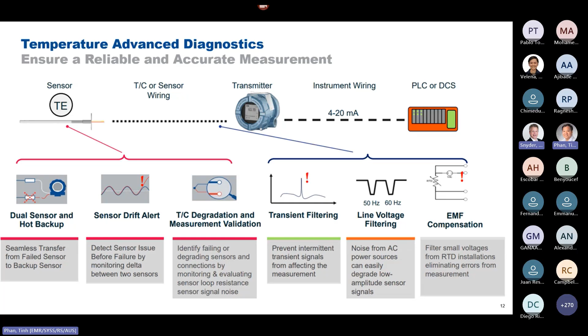Another nice thing is sensor drift. Over time your sensor gets corroded or builds up and starts drifting off. How do you deal with that? That drift is very important in a batch environment because your temperature and everything will be out of whack, causing quality issues. There are many other alert capabilities built into the device that get passed to the asset management system. If you understand HART communication protocol, it rides on top of your 4-20 milliamp signal, and it needs some way to detect and pull that information out so it can give you very valuable information in your asset management system.